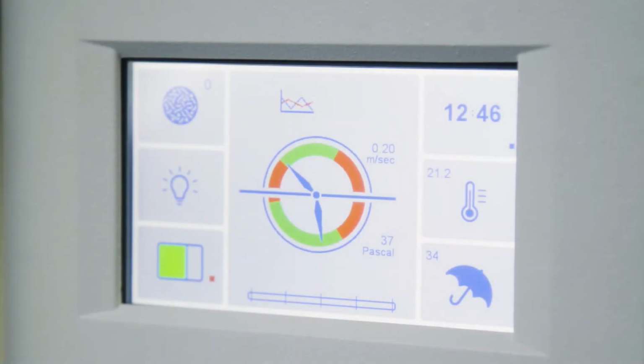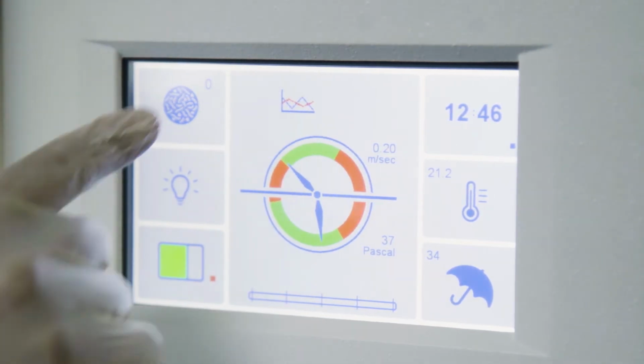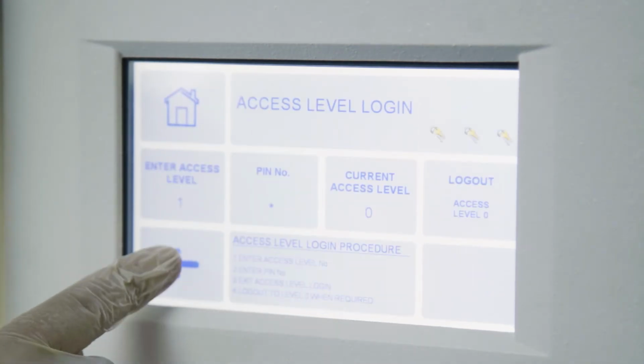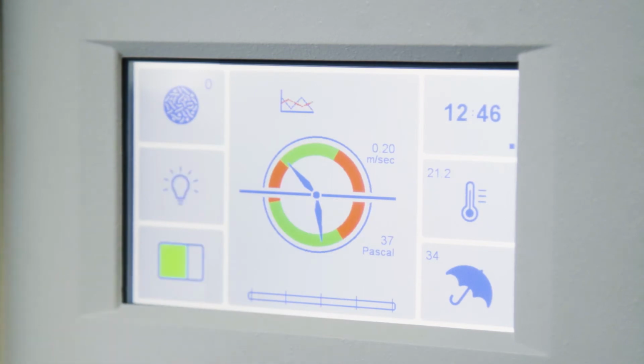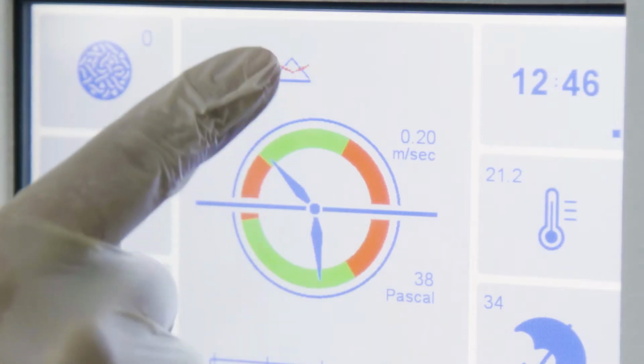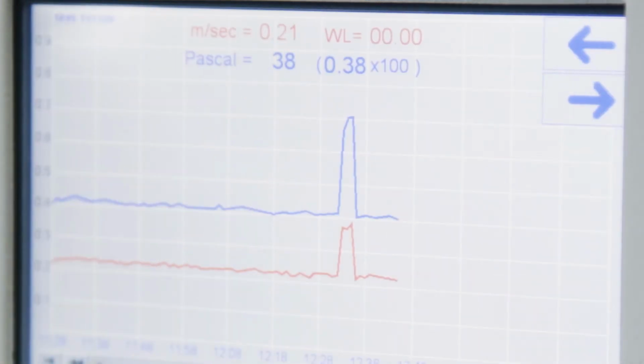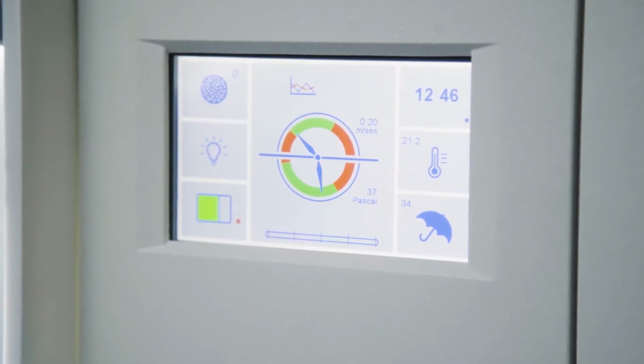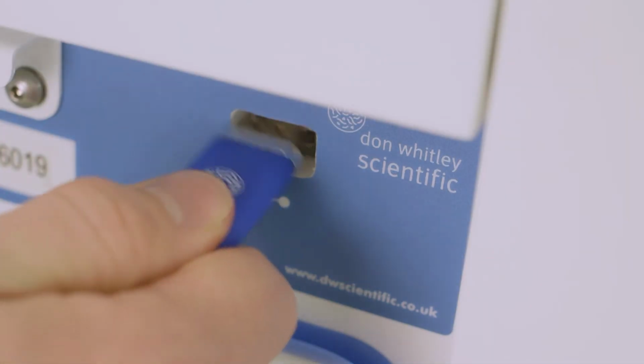Sterile air downflow speeds and all essential operating parameters are displayed in real time on the workstation touchscreen. The screen is PIN code protected and also allows users to control the airlock, access the event and data logs, and monitor the anaerobic conditions. The data and event logs are fully downloadable in a non-changeable format, facilitating batch traceability.